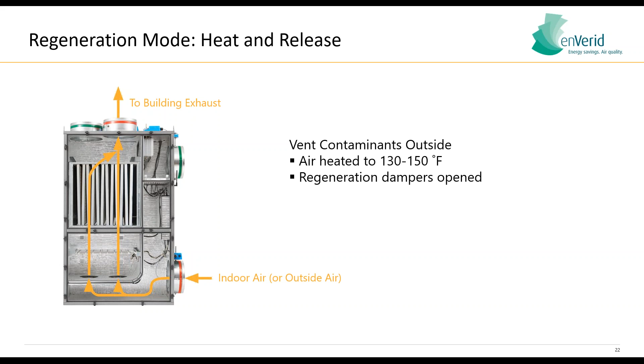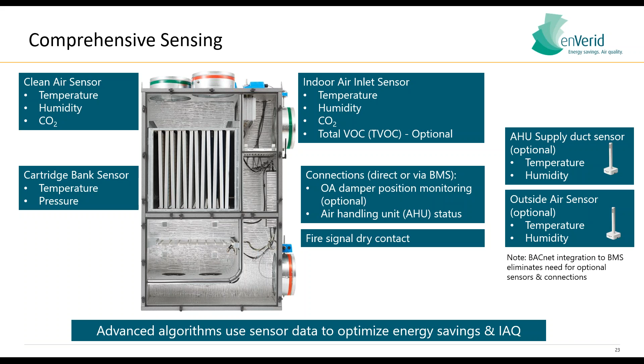So the unit is equipped with sensors. You can see on the right-hand side, we have temperature, humidity, carbon dioxide, and TVOC, total volatile organic compounds. And this will measure the inlet, so what's coming to the unit. And later you will see it displayed to the client 24/7. Now on the outlet, we have temperature, humidity, and carbon dioxide. We also have temperature sensors and pressure sensors inside the unit. Now we have the ability to do BACnet or hardwire. And so we receive a signal for the equipment to work, we receive the fire signal, and then we send signals back regarding the air quality, regarding energy savings, and the status of the unit. Also, we have a cellular connection, so we receive the data through our embedded cloud for monitoring and for alarms. Next slide, please.